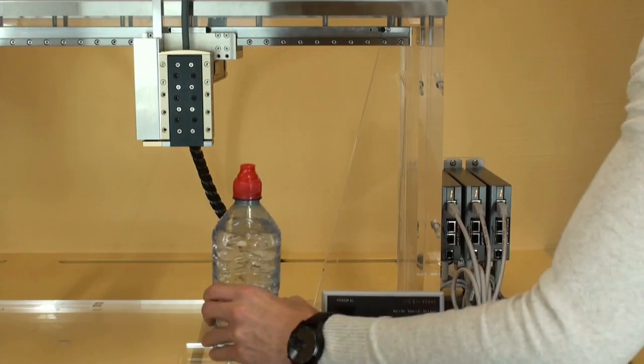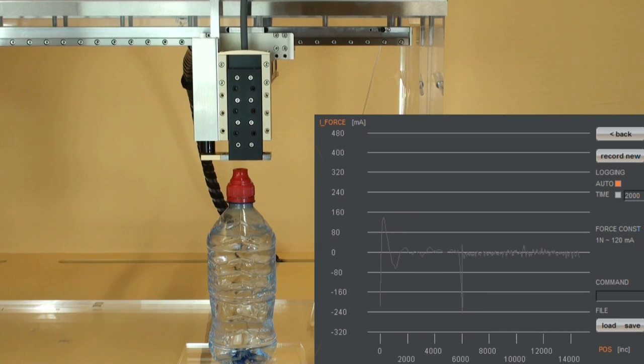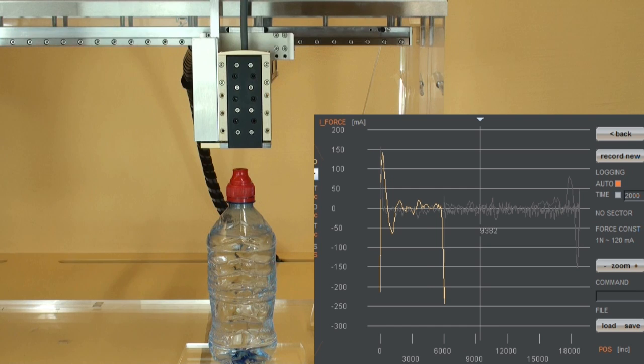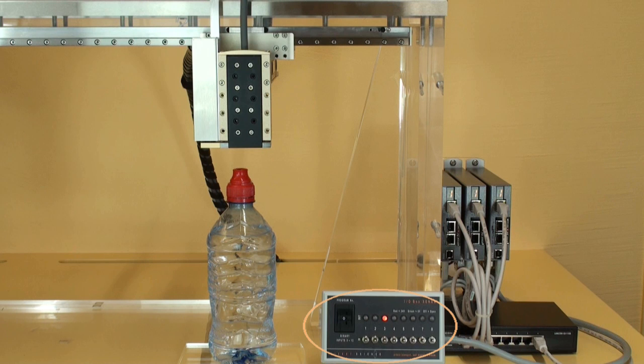On the other hand we can also see what happens when the lid is missing. In that case the linear motor does not detect the touching position and the sectors never apply. The missing of a lid is programmed on output 3.